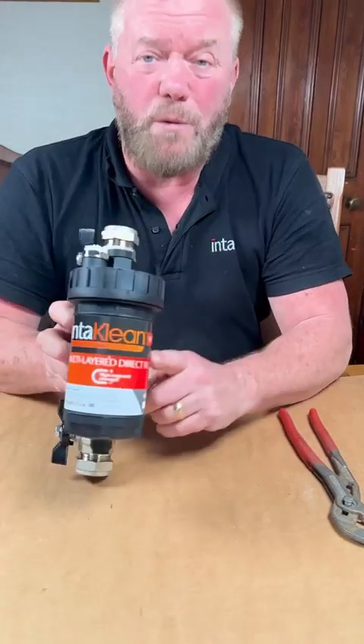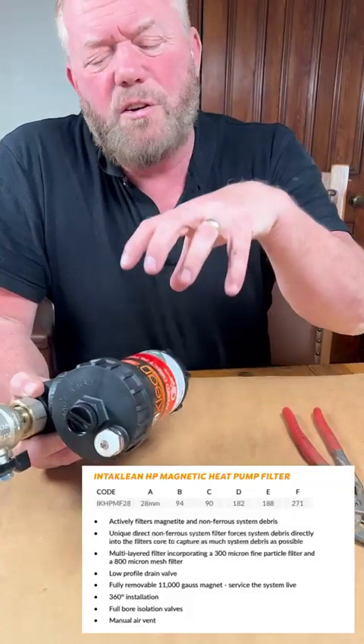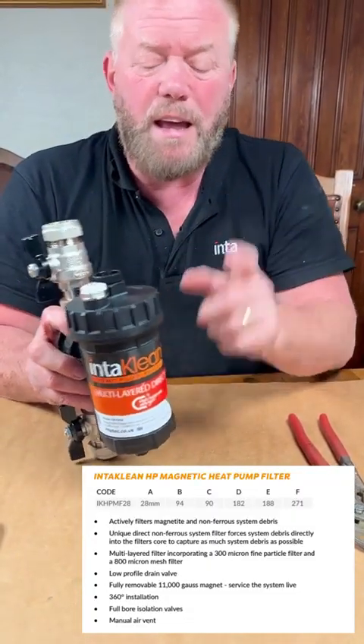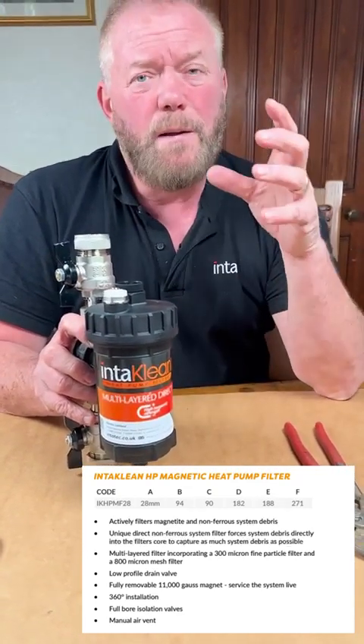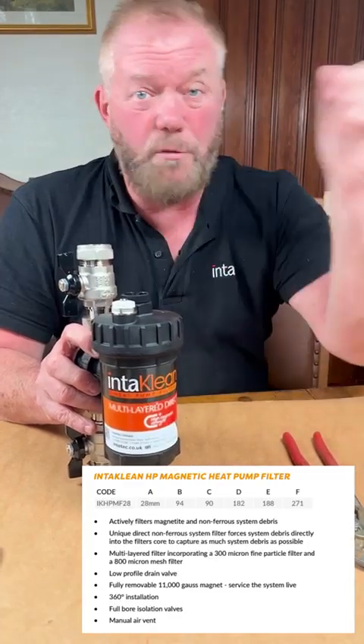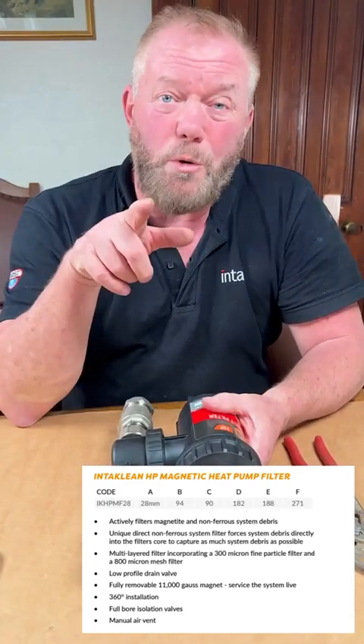What we can do to alleviate that is fit one of these — it's a cracking bit of kit. It's going to collect all the dirt. It's got an 11,000 gauss magnet in the top and a 300 micron filter in the bottom. So we're going to be able to clean all the debris out of the water and still keep flow and return flowing around your pipes, saving you from having to send your engineer out there and costing you loads of money.